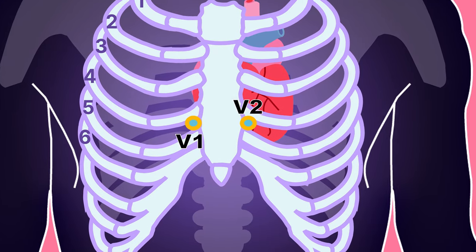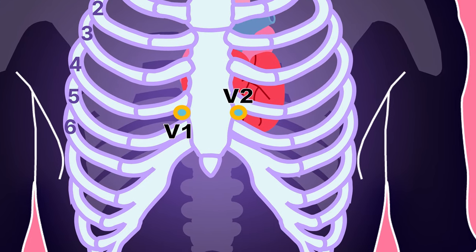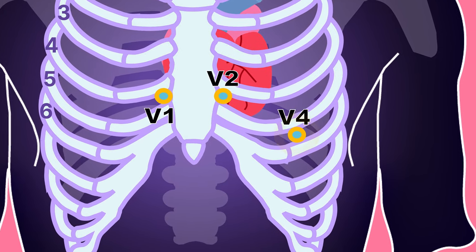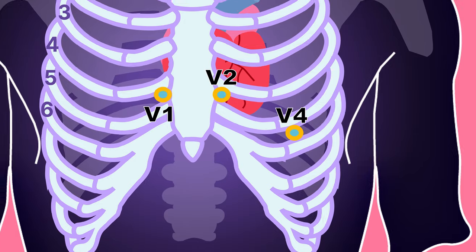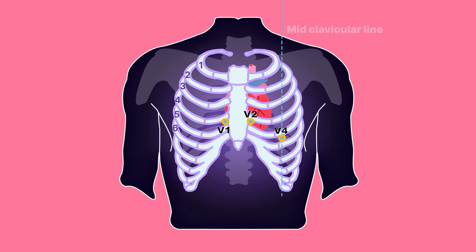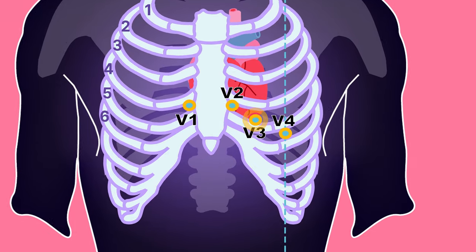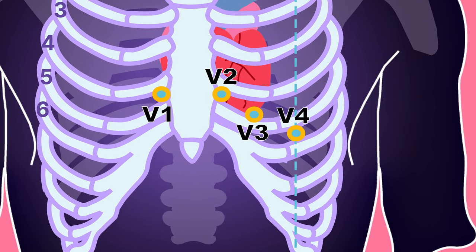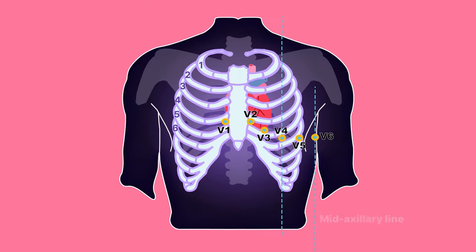V4 should be placed before V3. V4 is placed in the fifth intercostal space in the mid-clavicular line, as if drawing a line downwards from the centre of the patient's clavicle. V3 is placed directly between V2 and V4. V5 is placed directly between V4 and V6. V6 is placed over the fifth intercostal space at the mid-axillary line. V4 to V6 should line up horizontally along the fifth intercostal space.